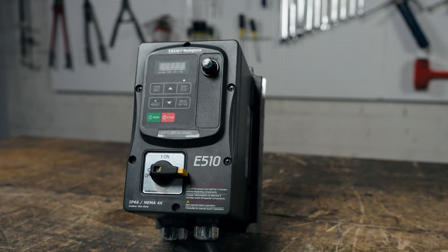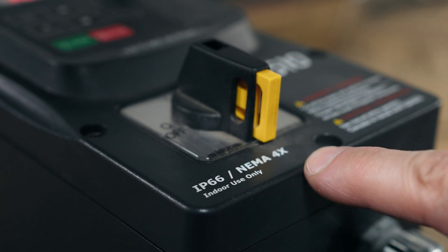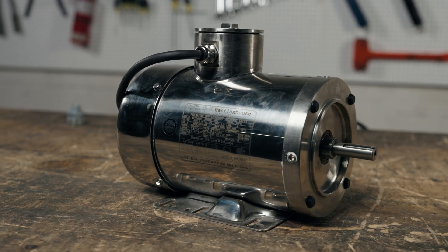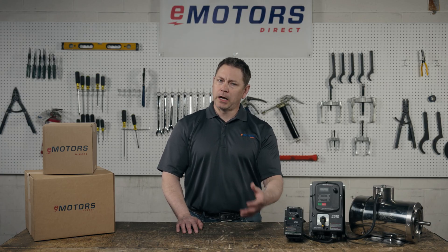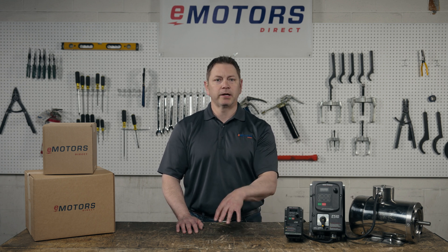The TECO E510 VFD series is considered a compact drive. The standout feature of the E510 is the ingress protection. These come in NEMA 4X enclosures, meaning they protect against dust, water, and corrosion. A NEMA 4X is equivalent to an IP65 or IP66. If you work in a facility that's washed down regularly, these are an ideal drive. The NEMA 4X enclosure will protect the internals of the VFD, allowing you to use this drive in food manufacturing and chemical processing applications with confidence.